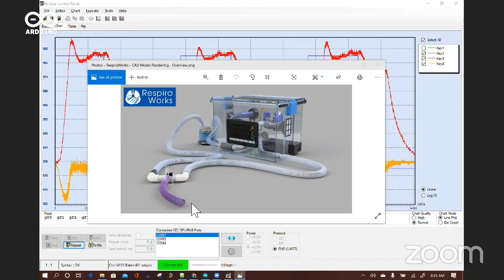This is difficult, as mentioned before, because the condition of the patient changes, the compliance and resistance of the lung changes. And so the design must be able to accommodate those. And so to pursue that, our goal is to provide 2 modes of ventilation. In particular, the assist control ventilation, which detects the patient breath, the patient inspiratory effort, and then provides supporting pressure at various degrees of support to change the amount of assist. And then also for patients that are incapable of breathing at all on their own, the pressure regulated volume controlled mode of operation, where the automated control of the ventilator controls the entire breathing cycle.